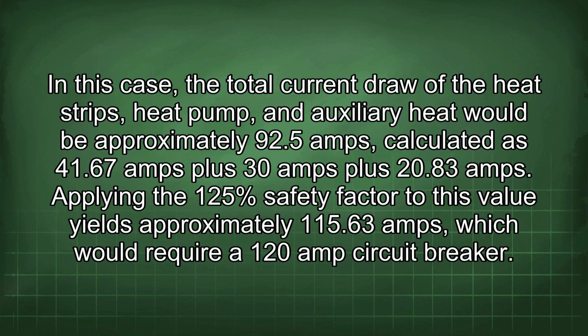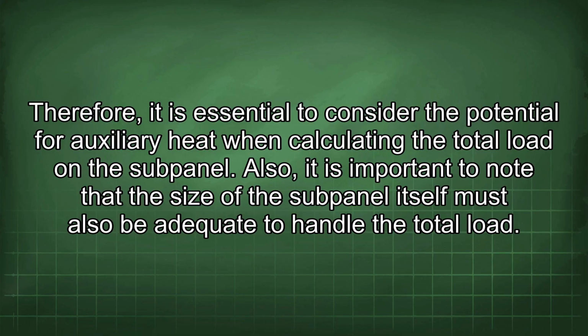In this case, the total current draw of the heat strips, heat pump, and auxiliary heat would be approximately 92.5 amps, calculated as 41.67 amps plus 30 amps plus 20.83 amps. Applying the 125% safety factor to this value yields approximately 115.63 amps, which would require a 120 amp circuit breaker. Therefore, it is essential to consider the potential for auxiliary heat when calculating the total load in the subpanel.